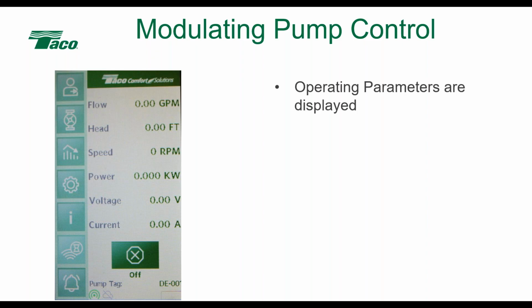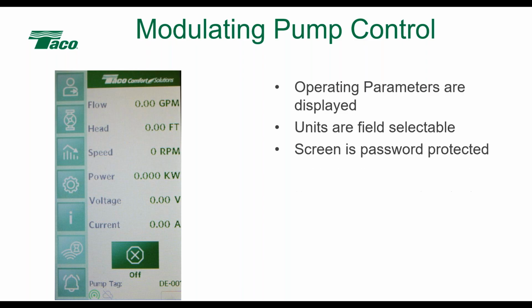So as you can see here on the screen, it gives you all the operating parameters. It'll tell me the flow, the head, the speed, the power, the applied voltage, and also the motor current. It also tells me the pump tag and all kinds of other things that it's capable of doing. You can select the units. So if you want to read head in PSI instead of feet, or speed in percentage versus RPM. Power, you can read in kW or horsepower. So you can select all that.